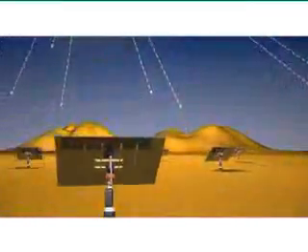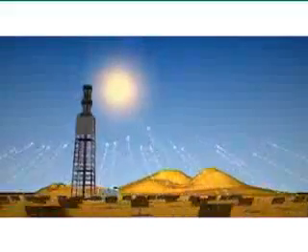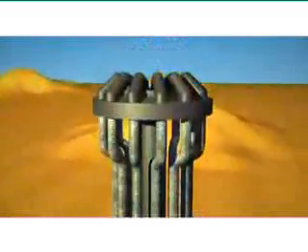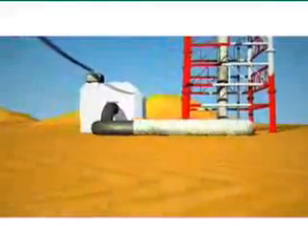The 1,600 computerized mirrors, or heliostats, concentrate the sun's rays and natural energy onto the boiler, which sits at the top of the 60-meter tower. This heats the water to over 1,000 degrees Fahrenheit. From the receiver, the superheated pressurized steam is conveyed to a steam turbine generator to produce electricity.